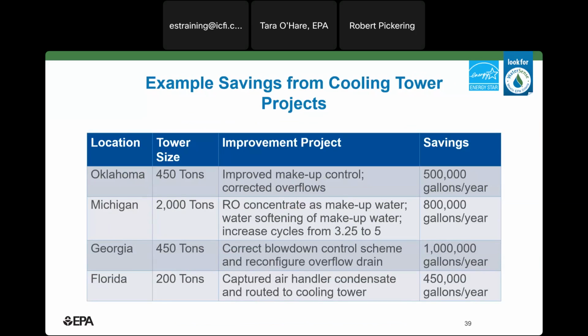And just to summarize, these are a few facilities I'm familiar with that implemented improvement projects, running a range of different things: some collecting air handler condensate, some improving blowdown control, some finding alternative sources of water like RO concentrate, installing water softening, and improving the cycles of concentration. You can see the scale of water savings that can be achieved by looking at your cooling tower and addressing some of its inefficiencies.